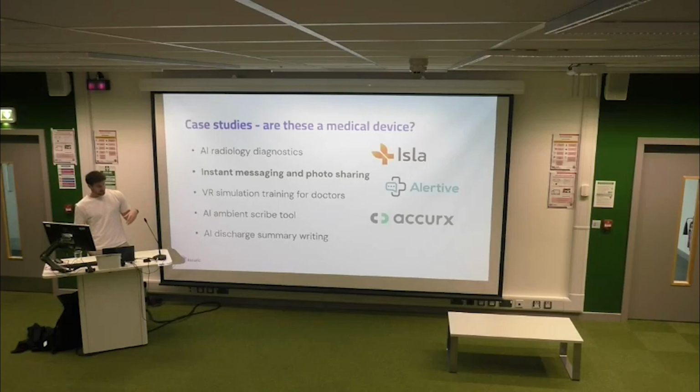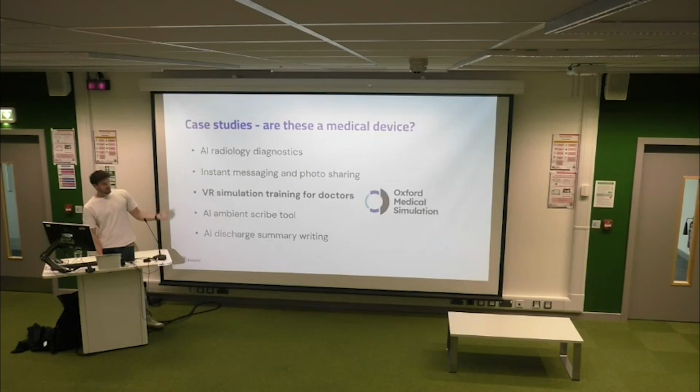What about instant messaging and photo sharing? Some classics, Accurx is a very well-known one. Would these communication tools be medical devices? Who says yes? Who says no? Yes, very good. So broadly, if they don't change the information, they wouldn't be a medical device. VR simulation training for doctors, one example company here. Medical device? Not a medical device. Yeah, so anything in training is not. Some companies choose to go down this route because it's not regulated.